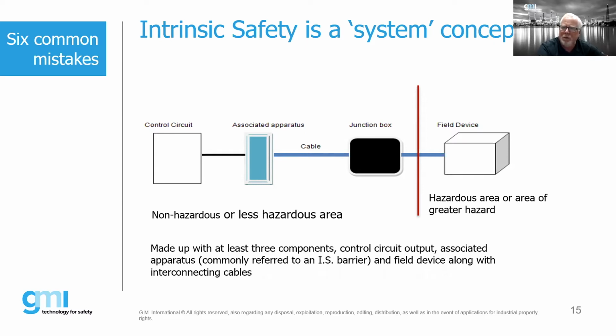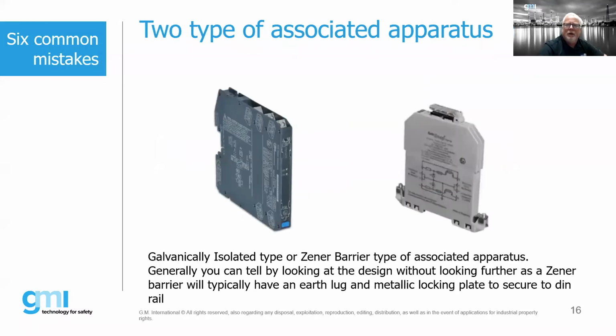So we typically take our control circuit, our cable, our junction box, our field device. Our barriers are considered to be what we would call associated apparatus. So if somebody uses the term associated apparatus, that's typically another reference to an intrinsically safe barrier. Sometimes we could have a junction box, a marshalling box of some sort that's located either in a safe area or a hazardous area, and then obviously the field device. But we also have to take into account the cable, and certainly whatever parameters we have from the control circuit. So that's our system concept. There are basically two main types of associated apparatus. On the left-hand side, you'll see what is called a galvanically isolated type product. On the right-hand side, you'll find a Zener barrier type.